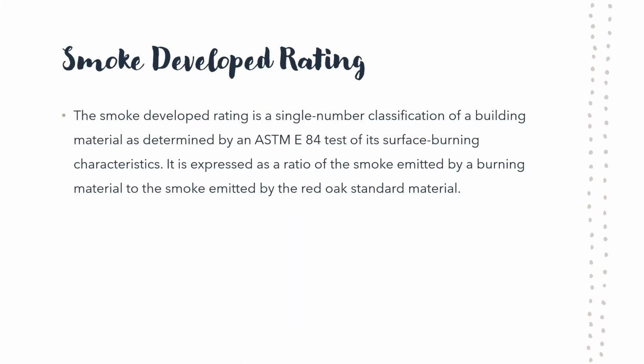The smoke developed rating is a single number classification of a building material as determined by the ASTM E84 test of its surface burning characteristics. It is expressed as the ratio of the smoke emitted by a burning material to the smoke emitted by the red oak standard material.